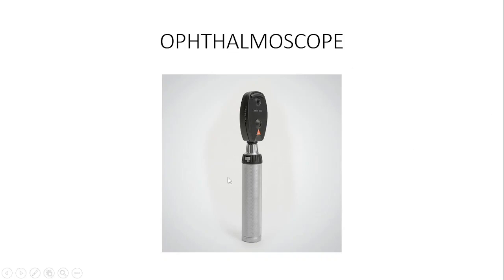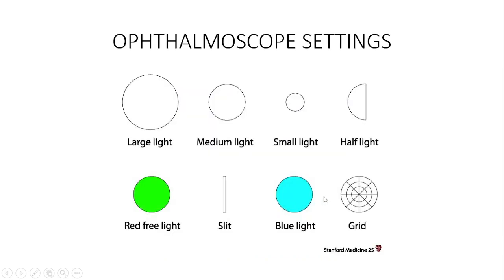The ophthalmoscope settings — when you want to do fundoscopy there are several lights and designs on the ophthalmoscope which you have to take note of. Use the large light when the pupil has been dilated with mydriatics and it is big. Use the medium light when the individual has not had any mydriatics in the eye.